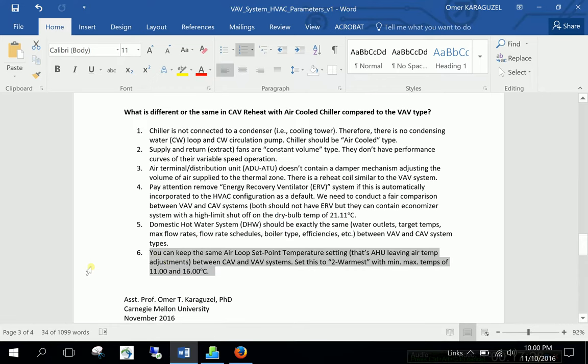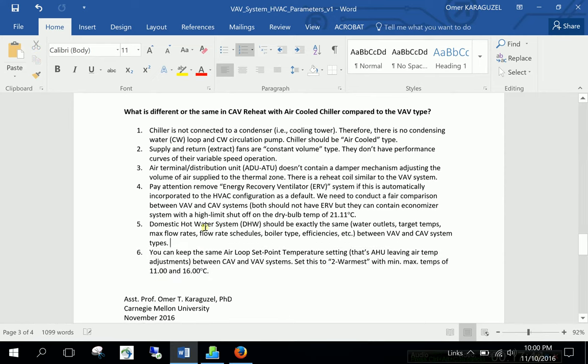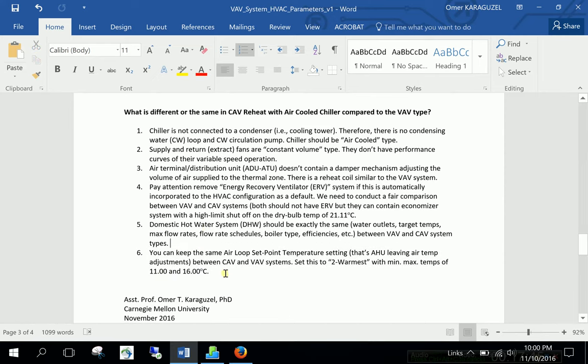You can keep the same air loop temperature settings. Like AHU's leaving temperature adjustments. For the VAV and CAV. Remember. We set this the warmest. The second one. With minimum and maximum temperatures. Eleven and sixteen degrees Celsius. And then this will finalize the second. So these are the main differences. Of course. I advise you to go out and read. Go out and find. Go ahead. Literature about these. Read about them. And you can come to us and discuss the differences. Operational characteristics.